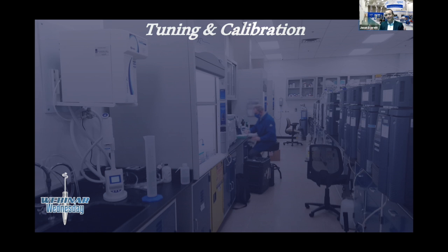field is critical. And that's probably one of the areas that I see a lot of programs focusing more on tuning, and we'll get into tuning here in a little bit, and probably a little bit less on calibration. I know there's calibration engineers whose full-time job is to go out into the plant and calibrate all the systems, all the field devices in the system. Then there's also workers inside the plant that calibrate the systems before they go into the field. So calibration, setting those components to their set point, set zero point or whatever, is very critical to process industry.